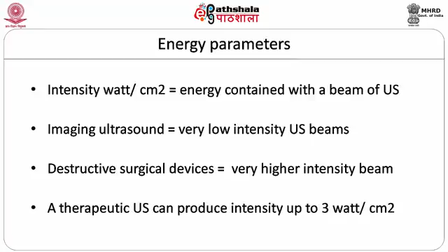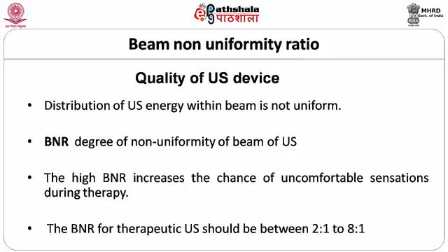The distribution of ultrasound energy within the beam is not uniform. It has high peaks and low peaks of intensity. The degree of non-uniformity of the ultrasound beam is measured as the beam non-uniformity ratio, which is the ratio of the intensity of the highest peak to the average intensity of all peaks. BNR depends on the piezoelectric quality of the crystal of the transducer. A crystal having high piezoelectric properties gives a more uniform beam and thus has lower BNR. A good transducer should have lower BNR. A high BNR increases the chance of uncomfortable sensations during therapy. The BNR of therapeutic ultrasound should be between 2:1 and 8:1.